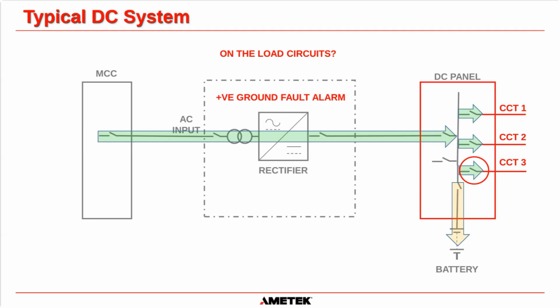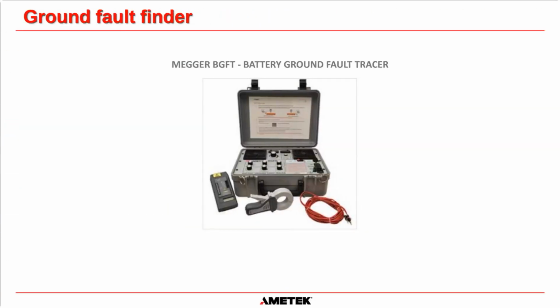But just always double check what you've been doing. So a lot of people are going to say, okay, Craig, that's fantastic. I'm not going to send my electricians out into the field, or as an electrician or a technician, I'm not going to go out into the field and open these circuit breakers. There must be another way to try and find these ground faults without switching the circuits off. And there actually is.